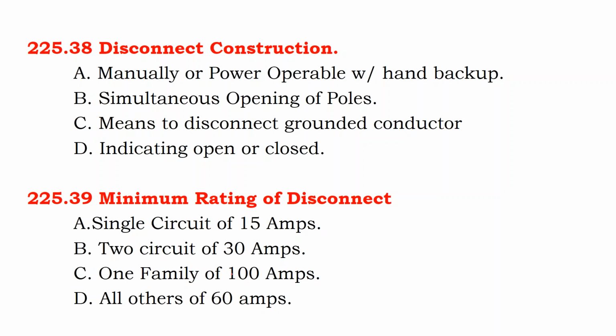So you might ask yourself, well, if I have to buy a disconnect switch and my choice is I have to buy a knife switch disconnect per the utility, maybe I can get ahead in the permitting process by calling the permitting office and saying, look, the knife switch disconnect is not a part of the National Electric Code. It's a jurisdictional requirement. What we want to do instead of putting in a knife switch disconnect is install an energy distribution panel, and it's going to have switches for all of these things, and even an automatic transfer switch that isolates the home when the power goes out. So do we have to spend additional money on a knife switch disconnect that really doesn't have any role other than to insert a failure point into the system, because we're already compliant in so many other ways?